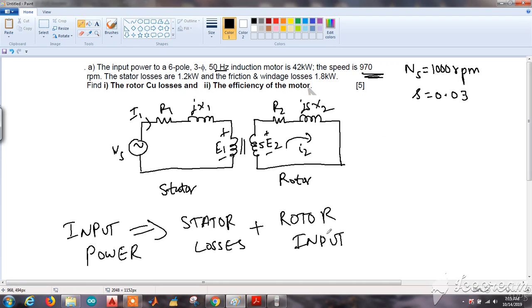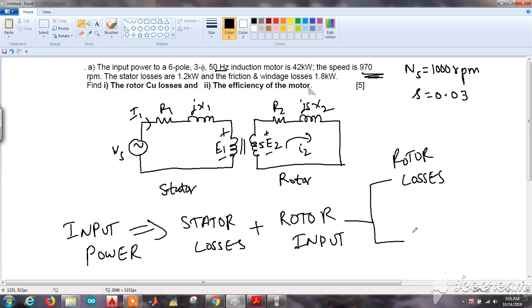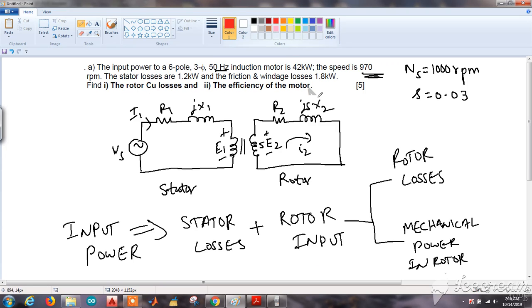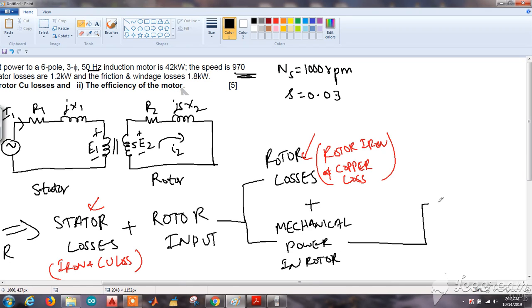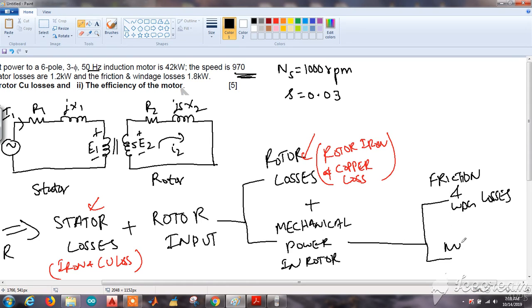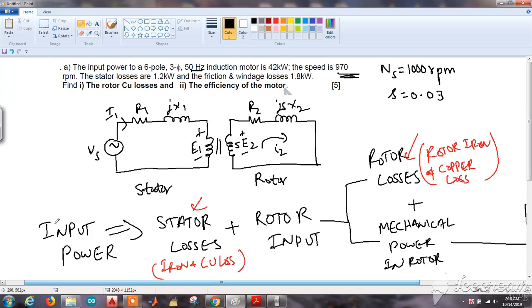The rotor input can be split into two parts: rotor losses — which include core (iron) and copper losses — and the mechanical power developed in the rotor. The mechanical power is further split into friction and windage losses, which occur in a rotating machine, and the motor output, which is P_out. So efficiency = P_out / P_in × 100.